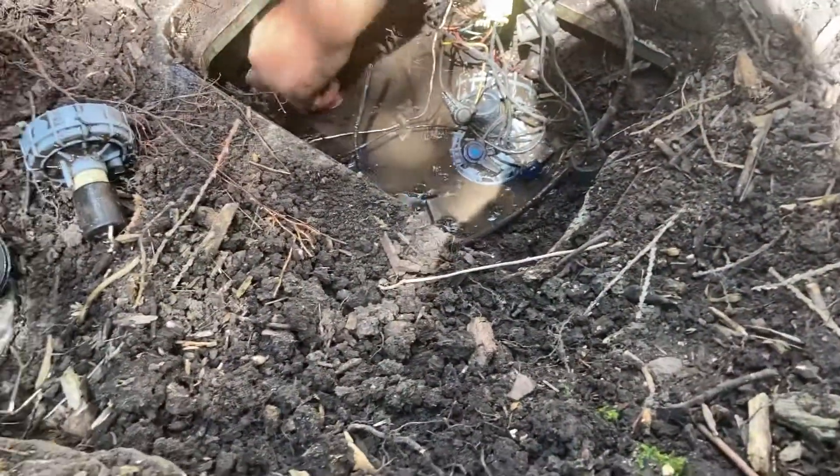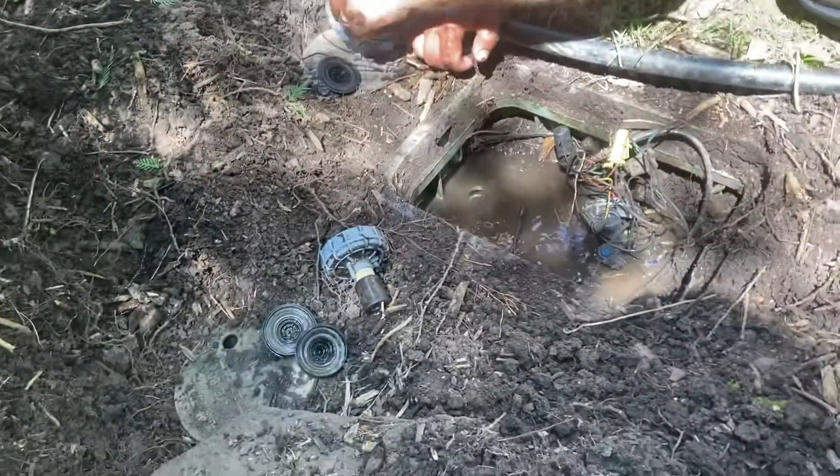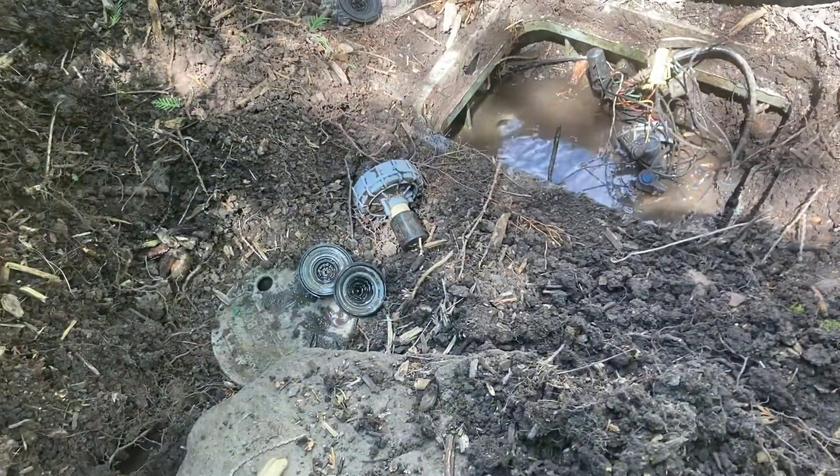Both of these valves were not working. That diaphragm's not as bad — that diaphragm has been replaced. Probably topped it out, used the same solenoid. That's why the wires are all twisted up.